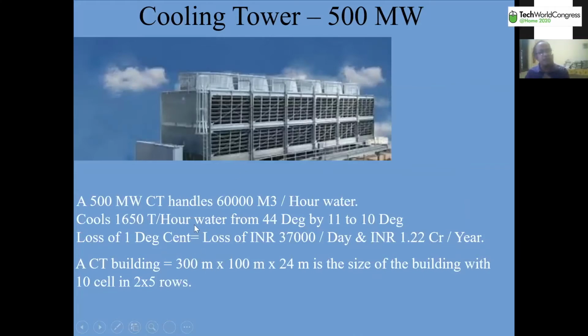Just imagine if steam temperature rises by 1 degree centigrade, there's a loss of 37,000 rupees per day. In a year, considering overhaul periods and unit stoppages, it becomes 1.22 crore rupees per year loss. So monitoring the CT temperature for each of these cells is very important.